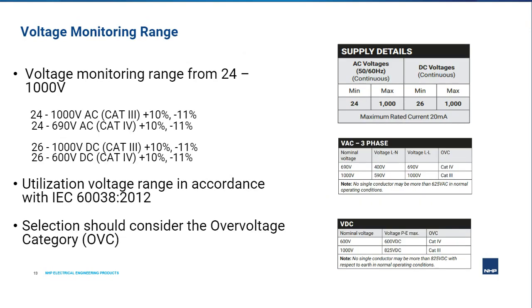Let's now look at the features of the REMLIVE unit in more depth, starting with the voltage monitoring range. We've already discussed how the REMLIVE DIN rail mount unit monitors the voltage level of the circuit. That's the circuit from the load side of a switching device and the actual load being switched. The latest update to the REMLIVE liveline unit can now monitor voltage ranges from 24 to 1000 volts AC and 26 to 1000 volts DC. The utilization voltage range of the REMLIVE unit is in compliance to the requirements of the IEC 60038:2012 standard. The tolerance limits of plus 10%, negative 11%, as indicated on the slide, are dictated by the standards and don't represent the actual limitation of the REMLIVE unit.